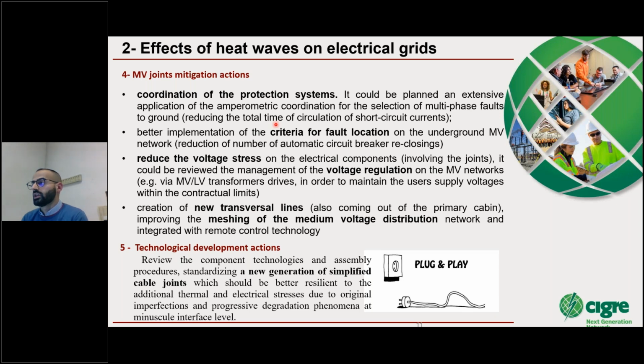For example, an extensive application of amperometric coordination could be planned for the selection of multi-phase faults to ground, reducing the total time of circulation of short circuit currents. Then a better implementation of the criteria for fault location on the underground medium voltage network, also reducing the number of automatic circuit breaker reclosings.